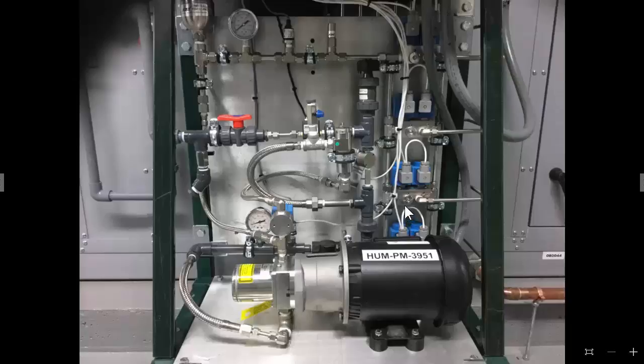But once you do decide to shut zone 3 off, say there's no demand anymore, and this was stuck open, it would actually continue to push water out the drain, because the dump valve would go to normally open, and this one stuck open, so it would go out to drain, and the system would shut down on low water pressure. So it could stay running for a while as long as it's calling, but if it's stuck open, as soon as it's not calling anymore, all the water would go to drain and it would shut off on a low pressure alarm. And let's say it was stuck closed, where it never would open up.